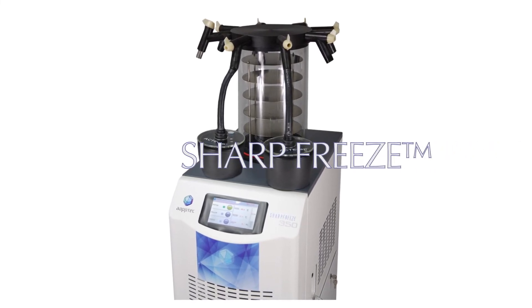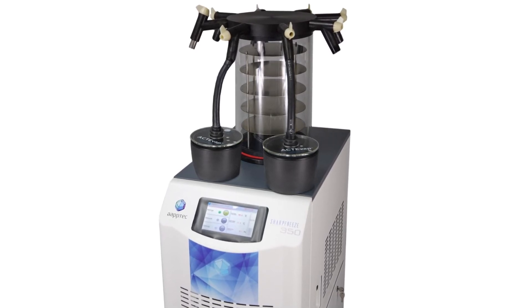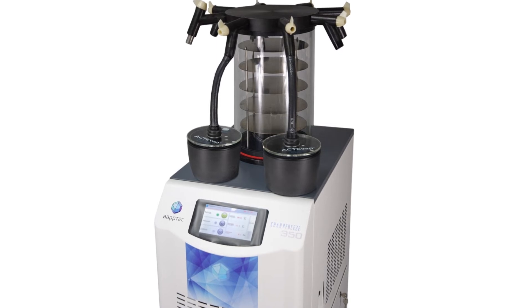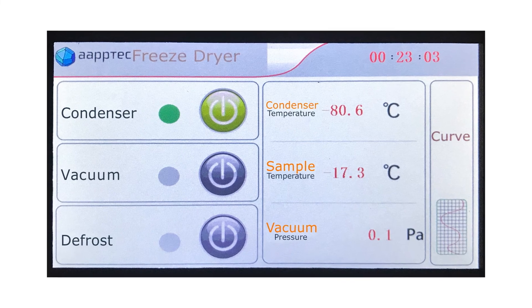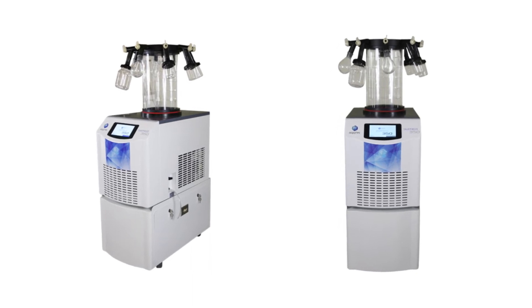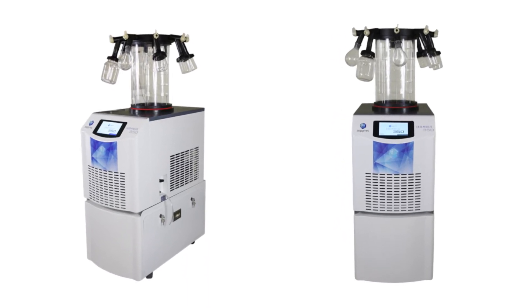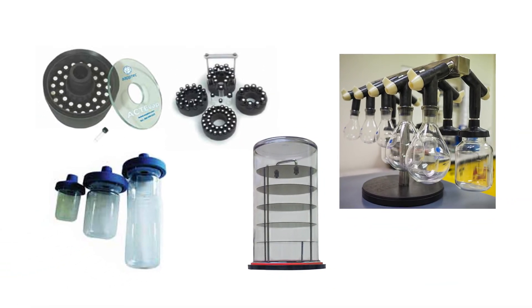Our SharpFreeze Lyophilizer is a flexible laboratory instrument with unsurpassed performance and reliability for peptides, proteins, nucleotides, PNAs, and DNAs. It is easy to control through an electronic control panel on the front of the instrument. The SharpFreeze is available in two models: one reaching minus 55 degrees Celsius and one reaching minus 80 degrees Celsius, both suitable for lyophilizing HPLC fractions containing acetonitrile or organic solvents. Each model comes in many sizes, including 2L, 4L, 6L, and 9L.